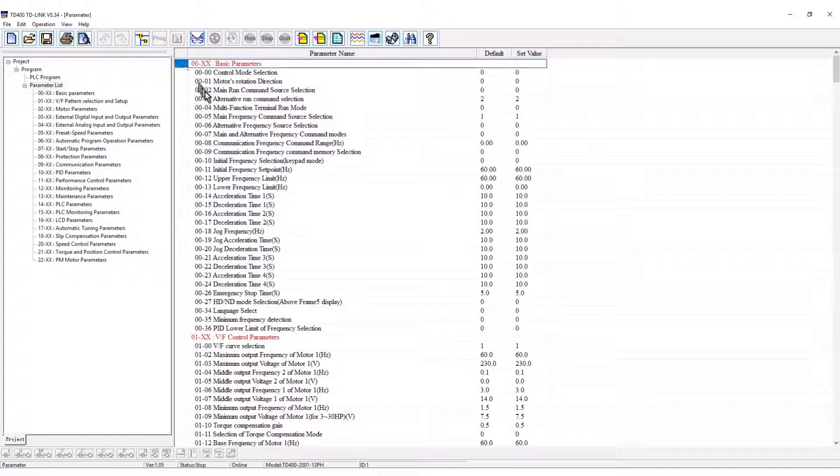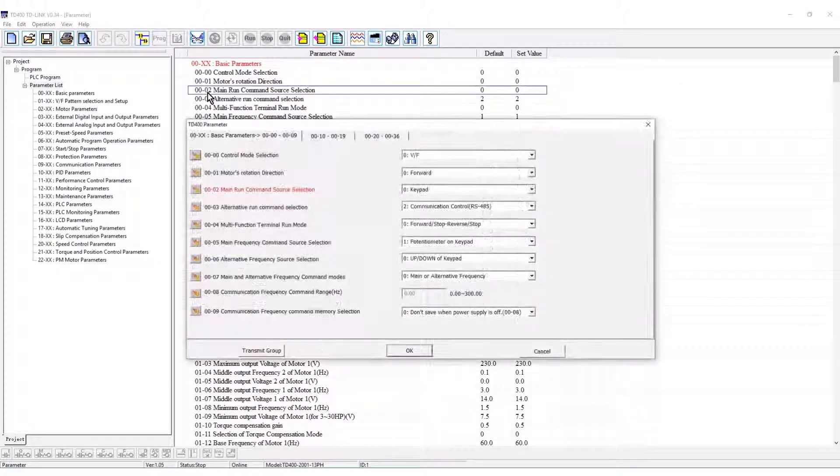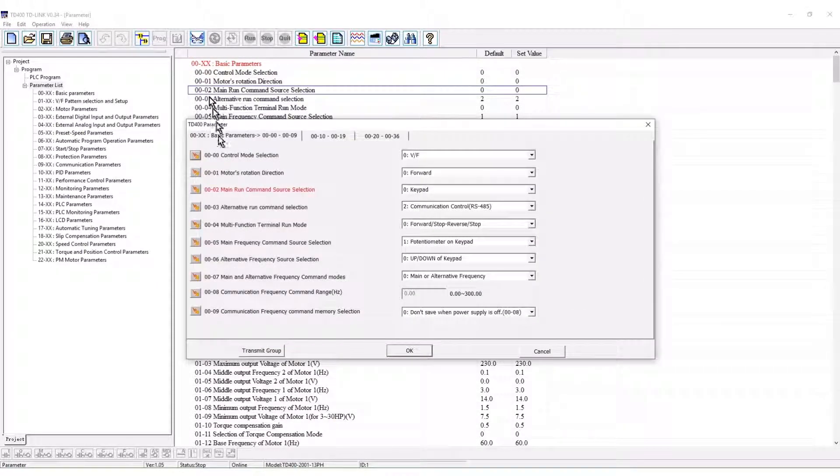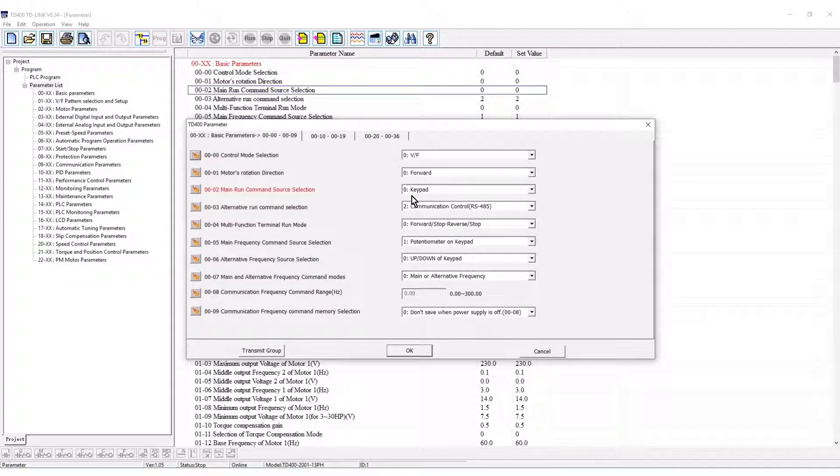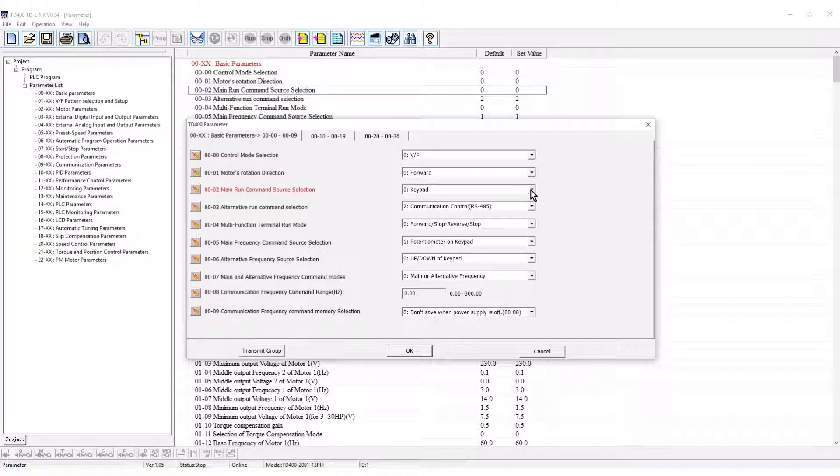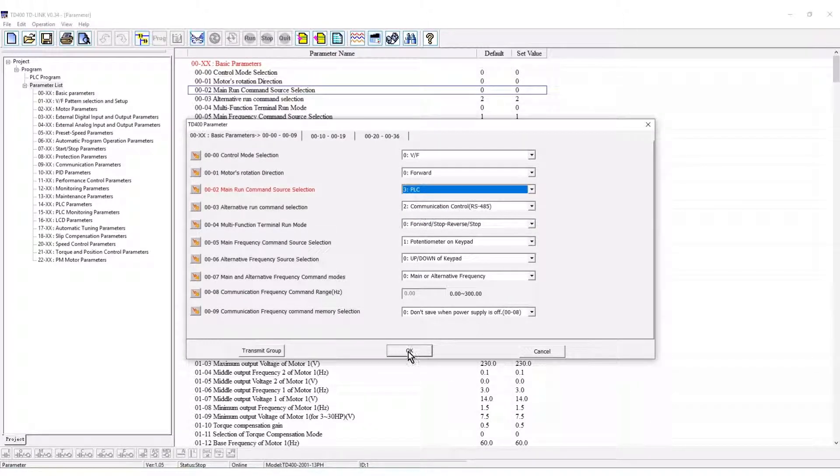Parameter group 0 will open initially. Parameter 2 is the main run command source. By default the VFD is controlled by the keypad. PLC control is selected. Click OK.